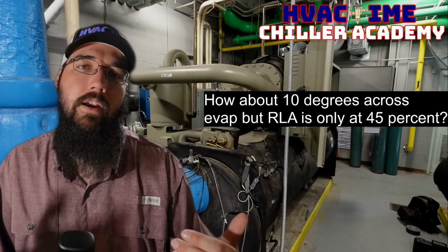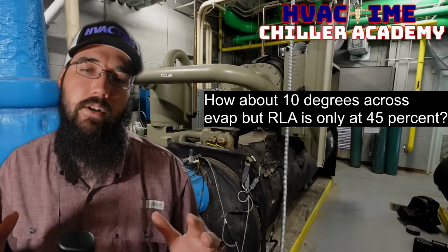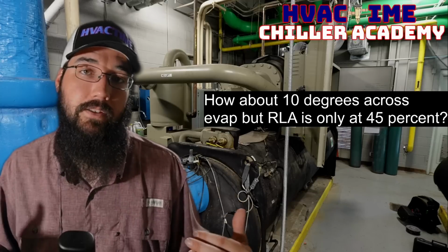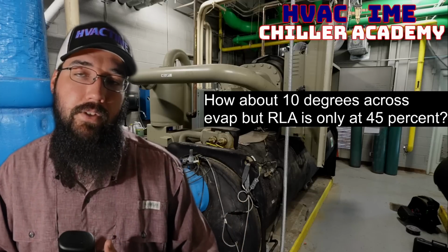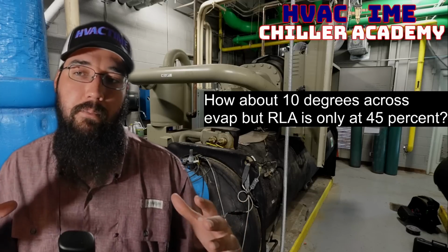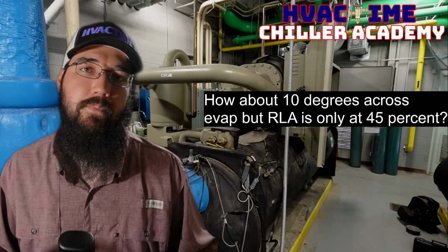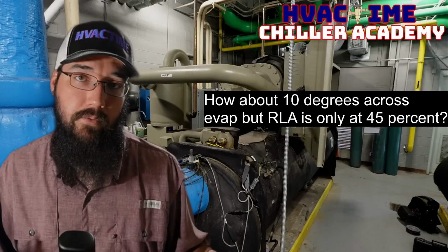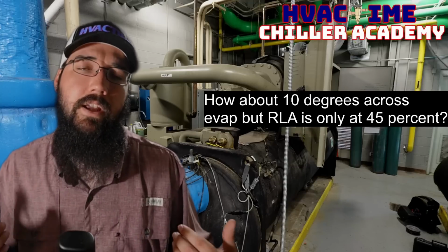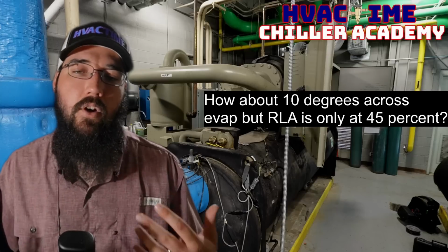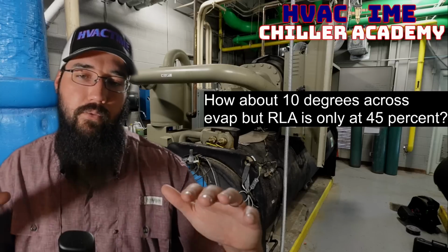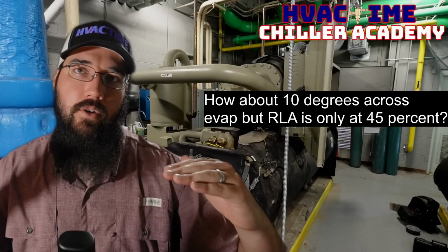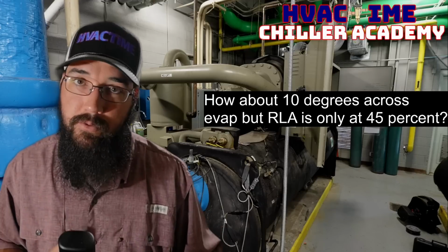So yeah, that would be my assessment if I had a condition that I would consider fairly loaded, a 10 degree delta and everything's correct in terms of design specs, but I've only got a 45% RLA. I would say that we've got a full load, but we're managing our lift really, really well. And that is enabling a really low RLA, which is where you're maximizing the coefficient of performance, the COP. We've got a really good COP at that point, which is all part of why, in a water cooled environment, if we can get that head pressure down and keep our condenser water under control, we can save a huge amount of efficiency.